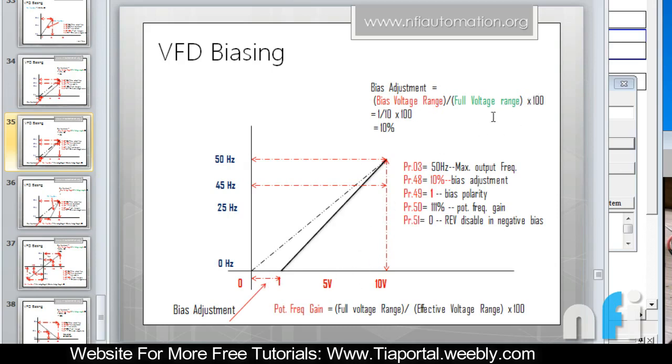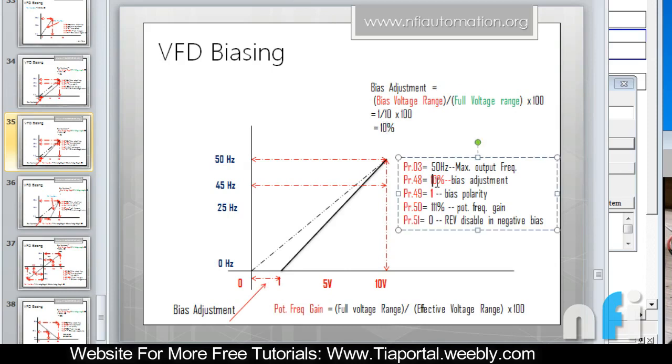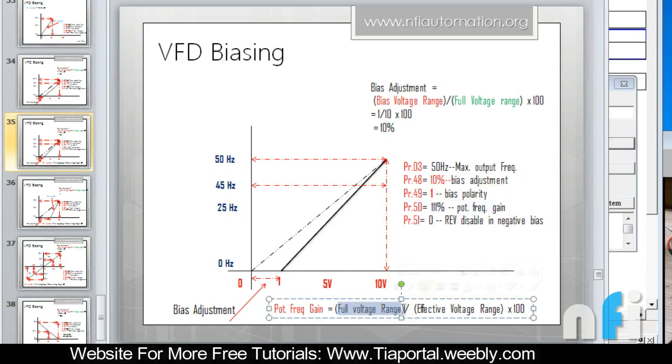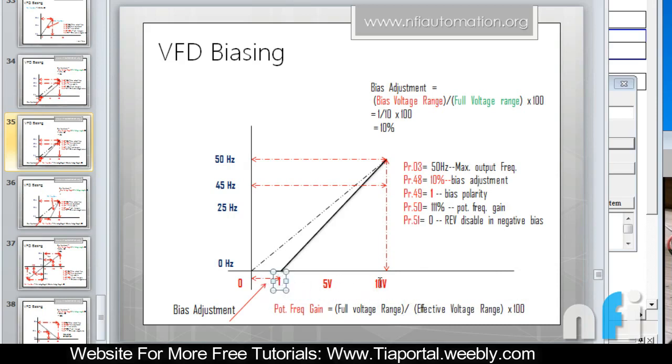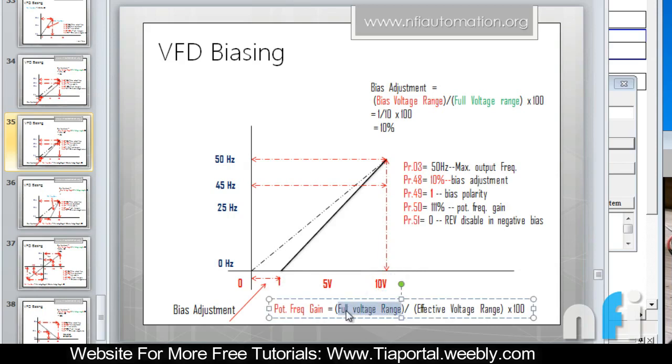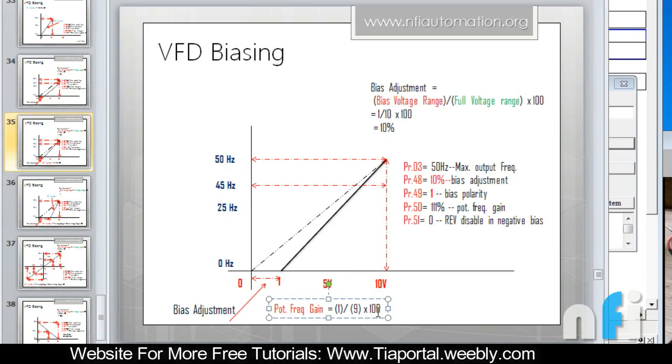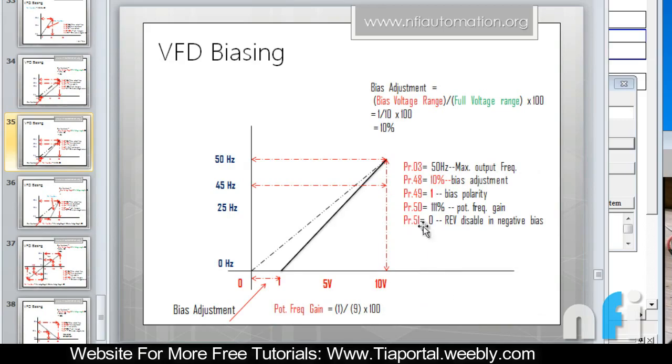The gain says full voltage range divided by effective voltage range into 100. Full voltage is 10 volt, effective is from 1 to 10 which is 9 volt. So this will be 10 divided by 9 into 100, so 1000 divided by 9 accounts to 111 percent.